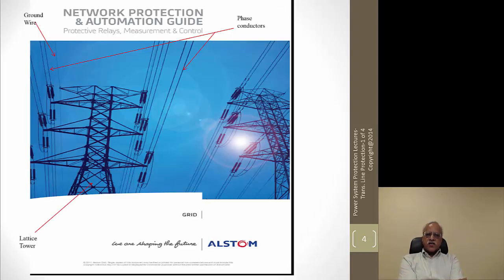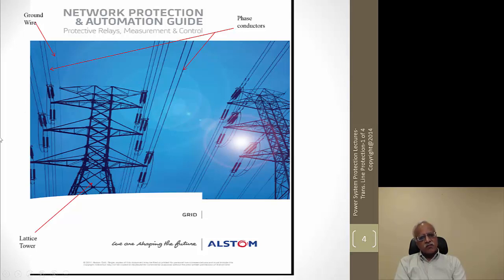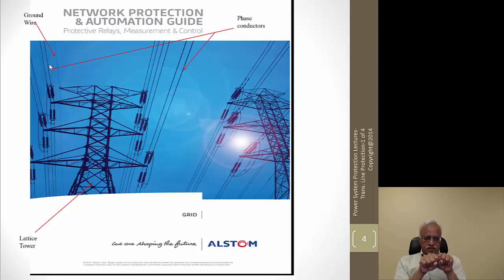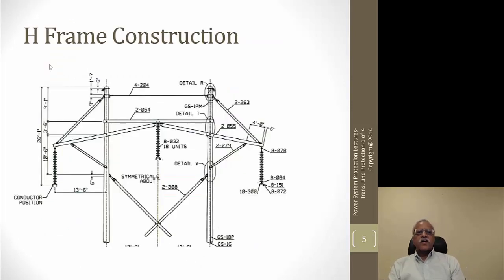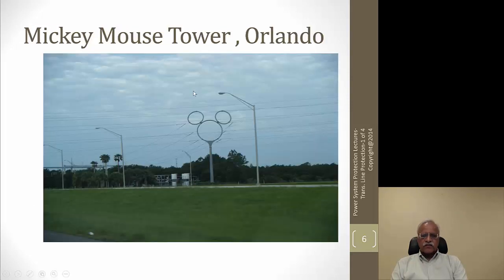This image from the reference book's front cover shows a steel lattice tower with a ground wire on top. There are two three-phase transmission lines on both sides of the tower, and each phase has two wires — a bundled conductor. The two wires with spacers between them reduce radio interference in EHV systems, or they increase current-carrying capacity. The H-frame wooden structure has phases hung below insulators. There is also a Mickey Mouse tower in Orlando near Disney World.